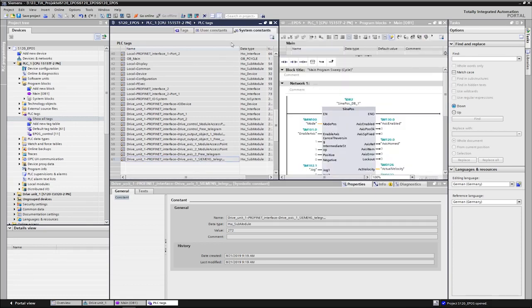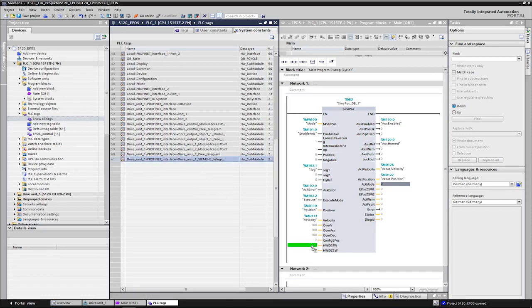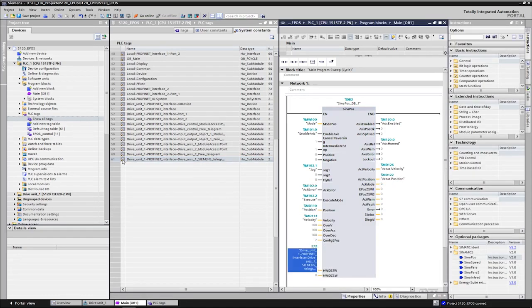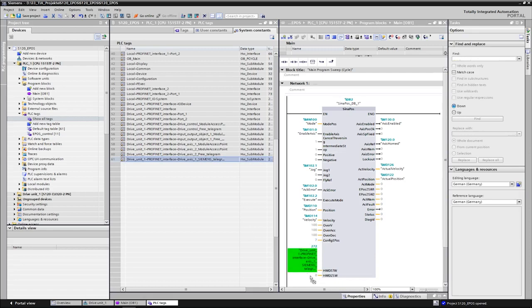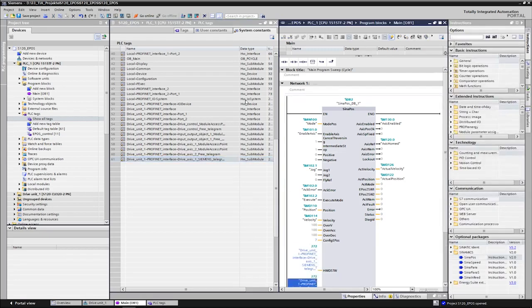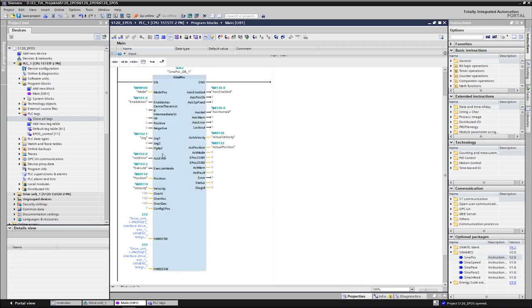From there we can connect the constants directly to the inputs of the block via drag and drop. The IDs are thereby symbolically addressed. If the inputs for the hardware ID are not correctly interconnected, the block will report an error and cannot communicate with the associated axis. The offline configuration has now been completed and we can load it both into the drive and PLC.